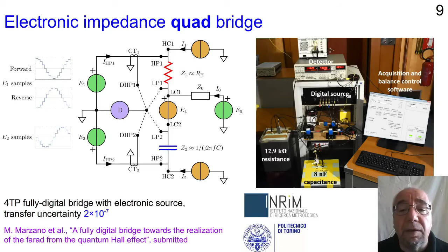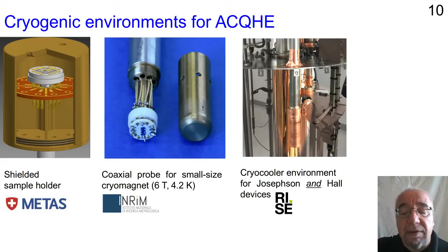To perform these quantum Hall measurements, it is necessary to develop dedicated cryogenic environments which can be suitable for AC quantum Hall effect measurements. You need shielding and coaxial cables in order to minimize the effect of stray parameters. On the left you see a shielded sample holder. The design is being now refined. In the middle you can see the realization of a coaxial probe which is devoted to perform measurements on a small size cryomagnet up to 6 Teslas. On the right you see a cryocooler environment that can host, with proper magnetic shielding, both Josephson and quantum Hall devices in the same cryostat. So it's able to host the Josephson bridge and the quantum Hall standards at the same time.